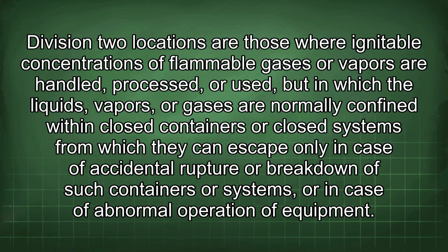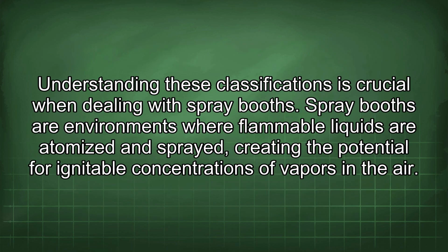Division 2 locations are those where ignitable concentrations of flammable gases or vapors are handled, processed, or used, but in which the liquids, vapors, or gases are normally confined within closed containers or closed systems from which they can escape only in case of accidental rupture or breakdown of such containers or systems, or in case of abnormal operation of equipment. Understanding these classifications is crucial when dealing with spray booths.